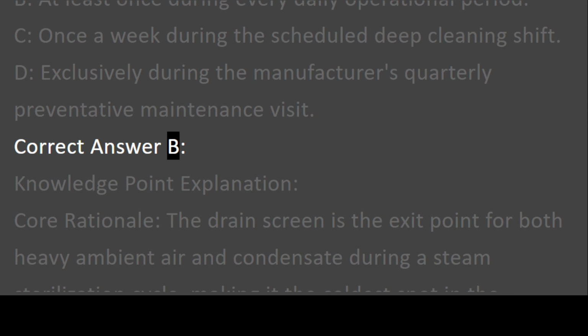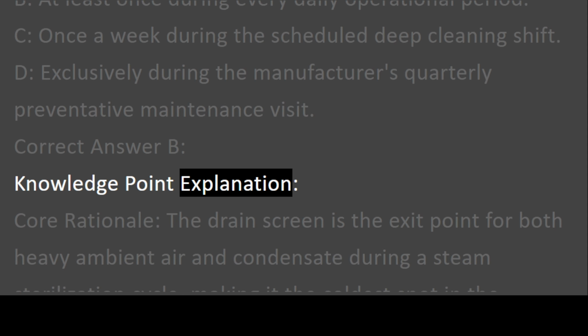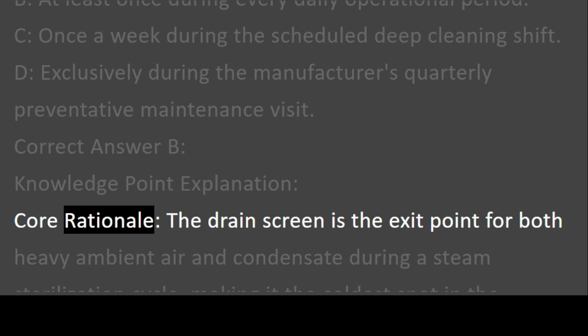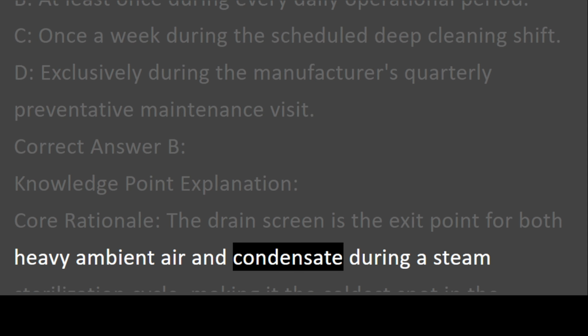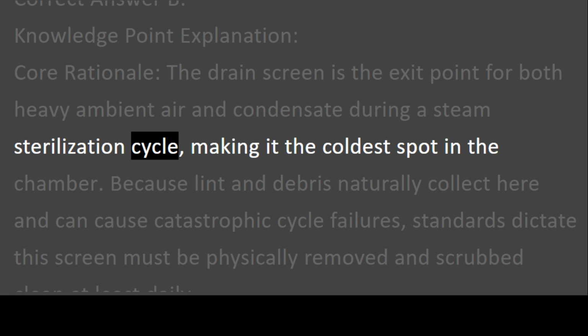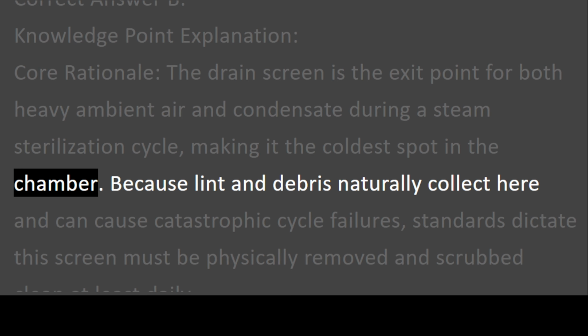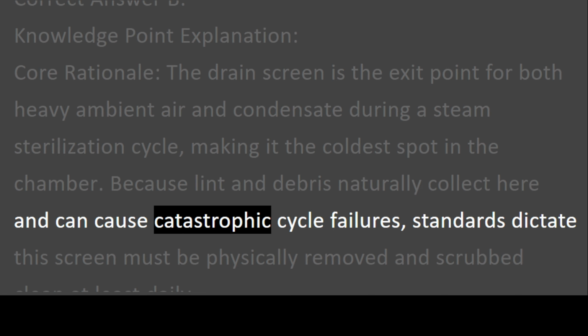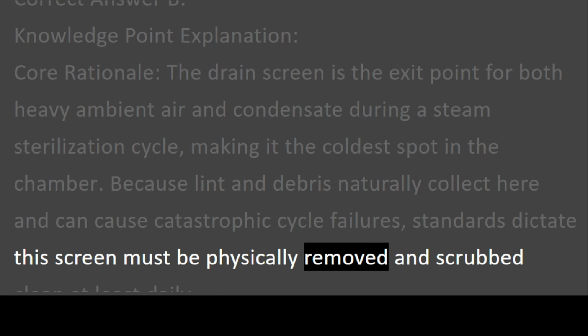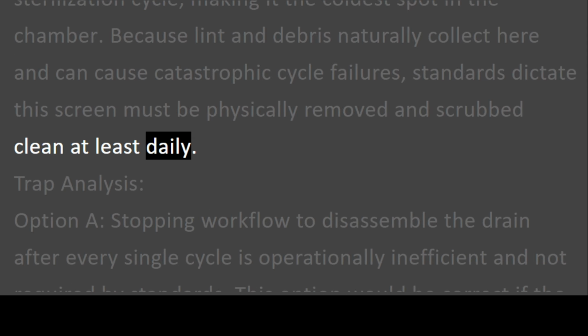Correct answer B. Knowledge point explanation. Core rationale. The drain screen is the exit point for both heavy ambient air and condensate during a steam sterilization cycle, making it the coldest spot in the chamber. Because lint and debris naturally collect here and can cause catastrophic cycle failures, standards dictate this screen must be physically removed and scrubbed clean at least daily.